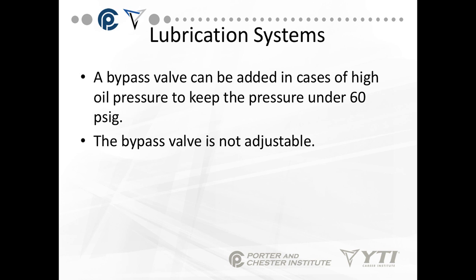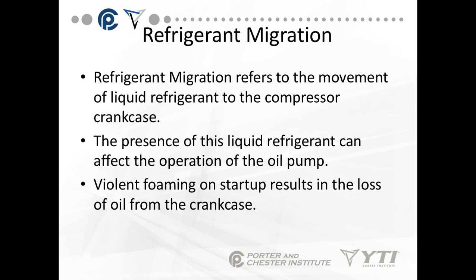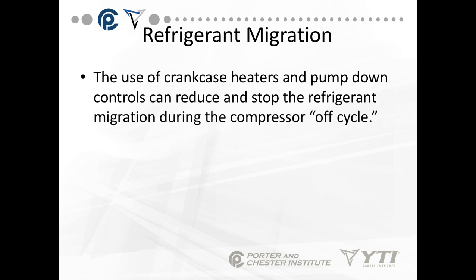A bypass valve can be added in cases of high oil pressure to keep the pressure under 60 PSI. That bypass valve is normally not adjustable. Refrigerant migration — we've talked about this before — is the movement of liquid refrigerant back to the compressor crankcase. It's one of the biggest issues when you have the condensing unit mounted outside in a cold climate. When the system is off, liquid refrigerant always migrates to the coldest spot. If the coldest spot is the compressor, it's going to mix with the oil and cause violent foaming on startup, pushing the oil right out of the compressor. The compressor will not run long without oil. We use a crankcase heater and a pump-down to reduce and stop refrigerant migration during the compressor off-cycle.